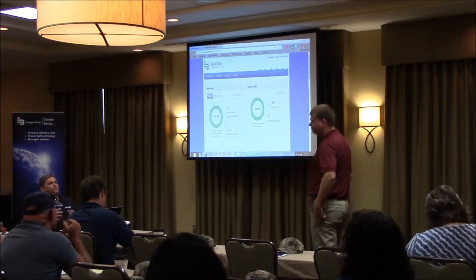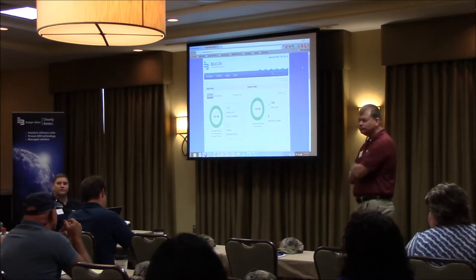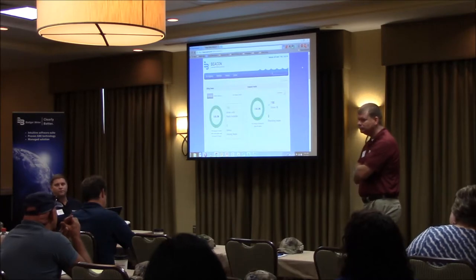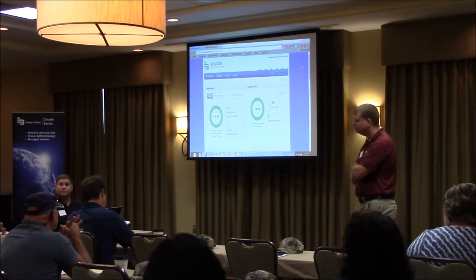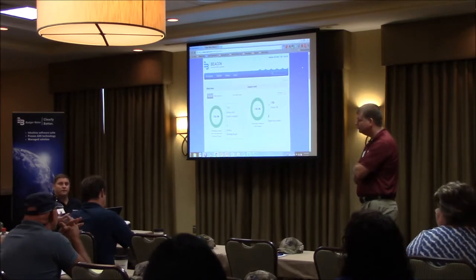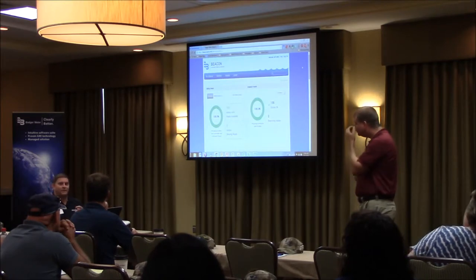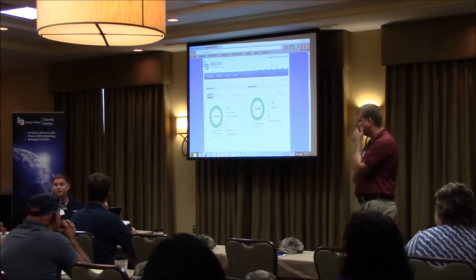Yeah, what happens is we've got a high resolution encoder on that, and currently we're only getting 6 digits from that encoder. So we're getting the reads, but it's only to the 1,000 gallon resolution on that. And that is a custody transfer meter. The town is purchasing that water from us, and so they want more accuracy. And so we're still working on that.